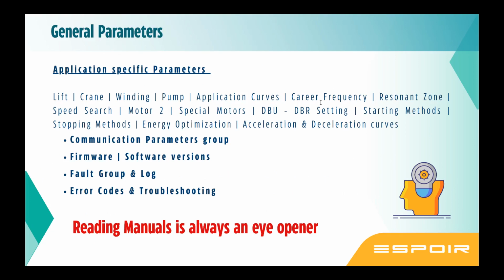Drives up to 15 kilowatt or 18.5 kilowatt have a default built-in dynamic braking unit. Above that, you need to buy an external DBU. The DBR you need to buy externally and connect externally. Then there are energy optimization features you can use for an energy saving application. Acceleration and deceleration patterns are available. You can use them for different applications.